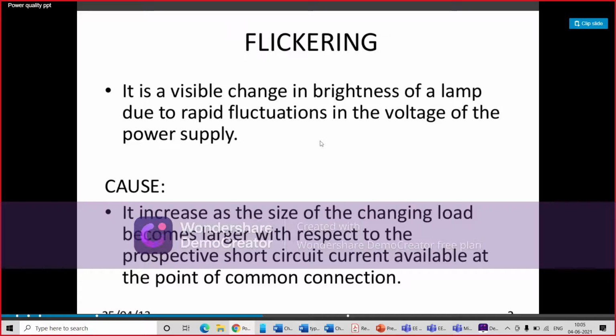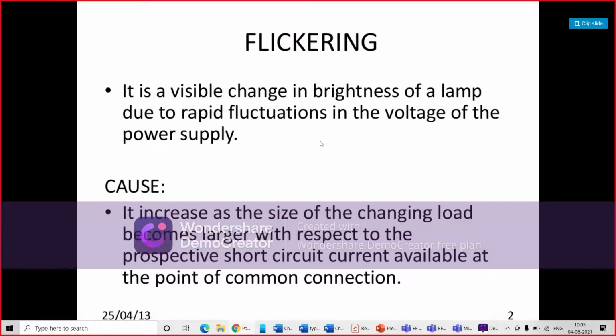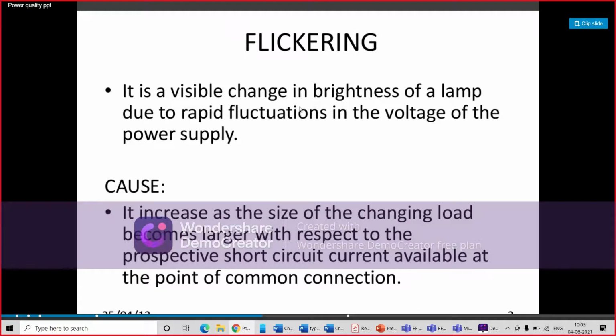Flickering, you must have seen this phenomenon sometime in your home also, when your lights and all these things are switched on and off very frequently. So it is a visible change in brightness of a lamp due to rapid fluctuation in the voltage of the power supply, and its main cause is that it increases as the size of the changing load becomes larger with respect to the prospective short circuit current available at the point of common connection.